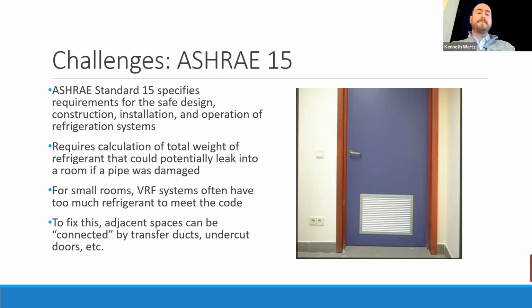condensers and indoor units in every classroom, if you've got a small enough classroom that the amount of refrigerant could fill the whole room, then you potentially run into a safety issue. The way you generally would fix that is you put these transfer grills in doors or in the walls. You could undercut the doors to try to provide some space for the refrigerant to get out into a different space, so that there's enough free oxygen for people to escape safely. But again, it's something that comes up on these projects that you want to be aware of and try to mitigate before it becomes an issue.